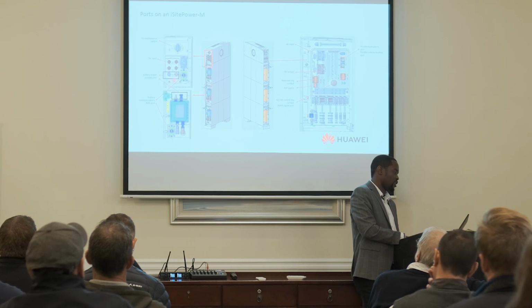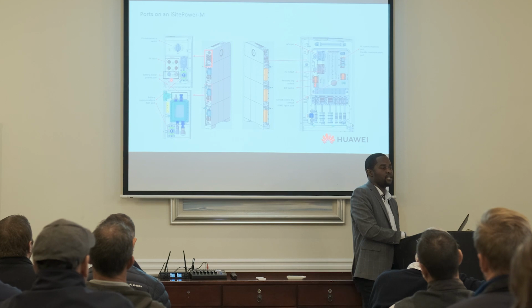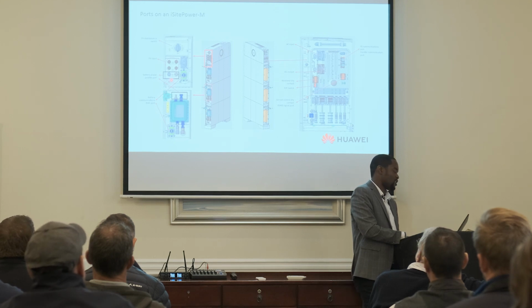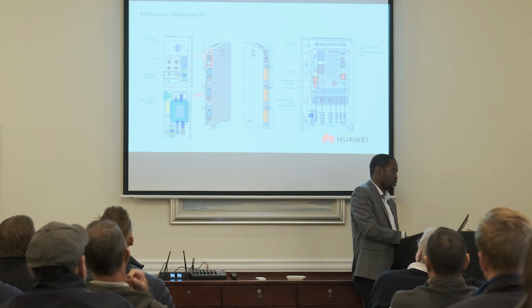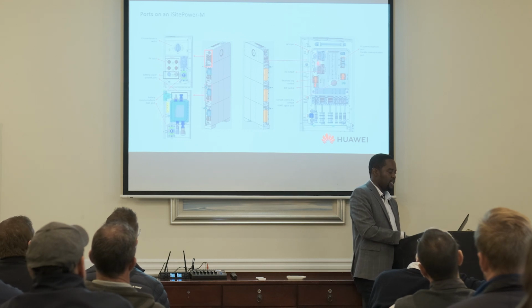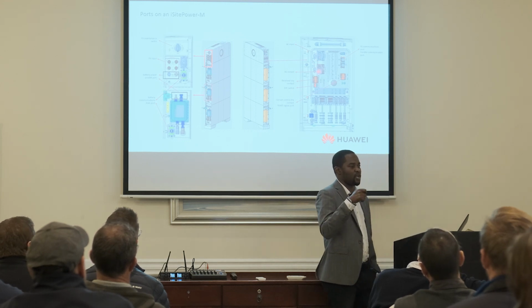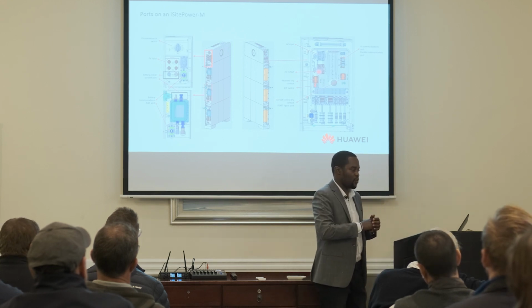Then your battery pack, this is for your communication modules, to loop your communication wire from battery to battery and up to the inverter. Then you've got your battery input, which is also MC4s, 6mm DC cable, normal 6mm, because it's a high voltage and low current. Right, that is on the left side of your inverter. Then on the right side of the inverter, you have the AC in and the AC output. These are actually terminals that you plug in, so you can take them off the inverter, then wire them away from the inverter, so you're not terminating on the inverter.